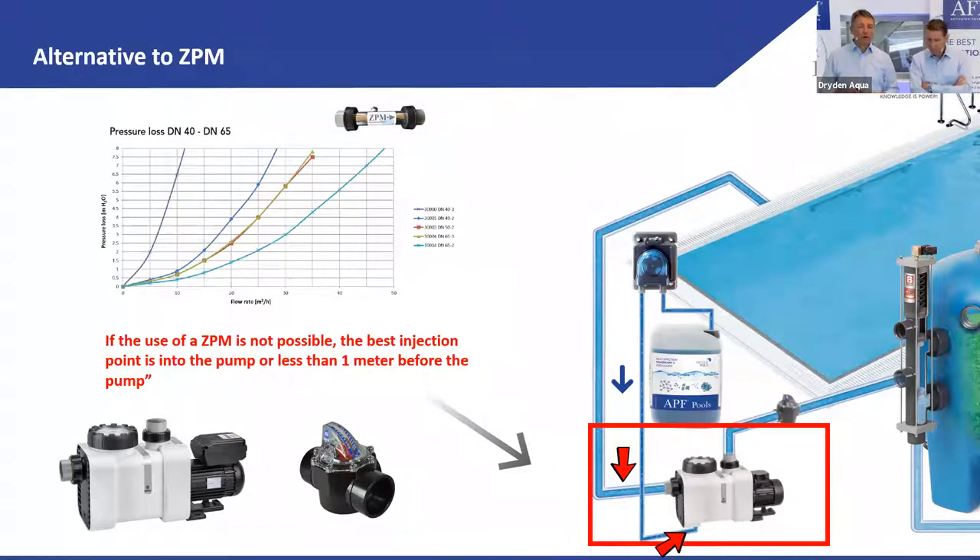For me, the longer the reaction time before reaching the filter, the better. Even if you choose not to dose right before the pump, at minimum dose just after the pump with the maximum pipe run before the filter. The longer the reaction time the better — but really the best injection point if you can't use a ZPM is just before the pump.